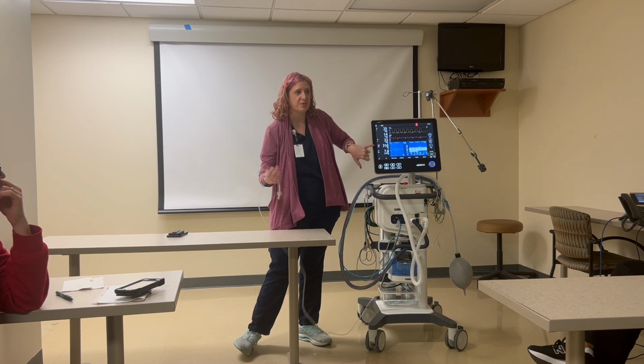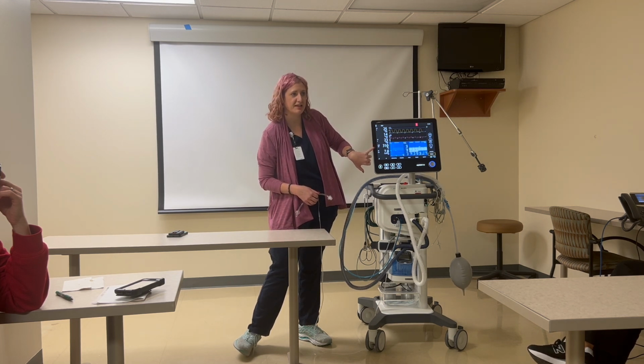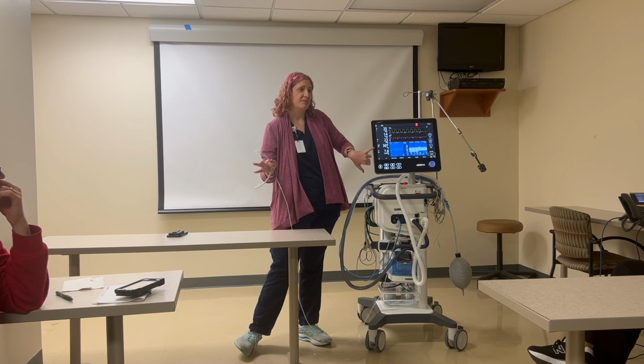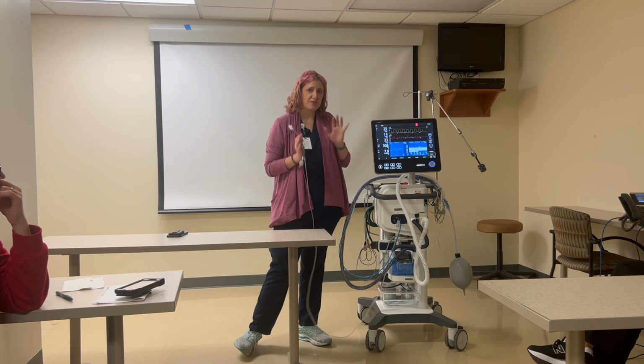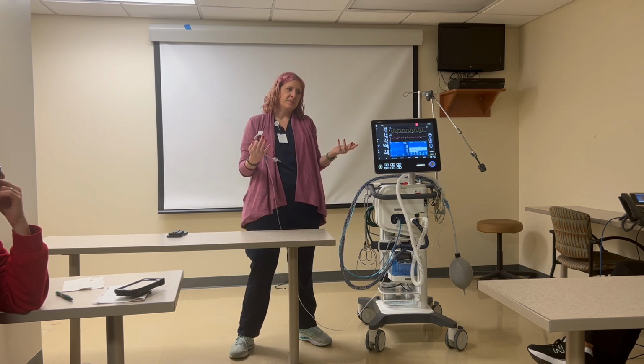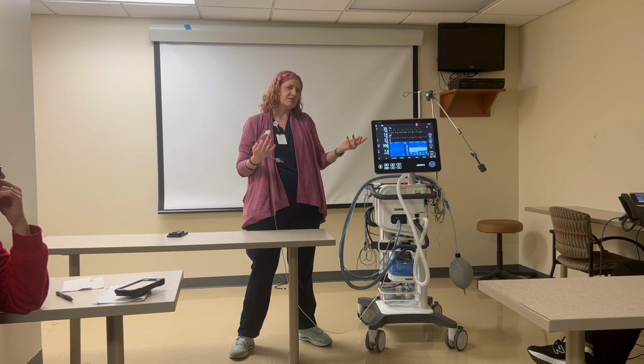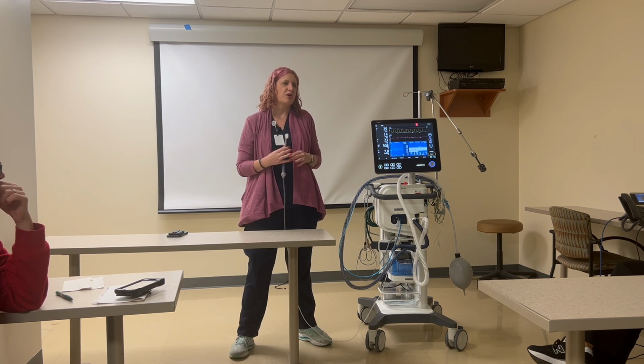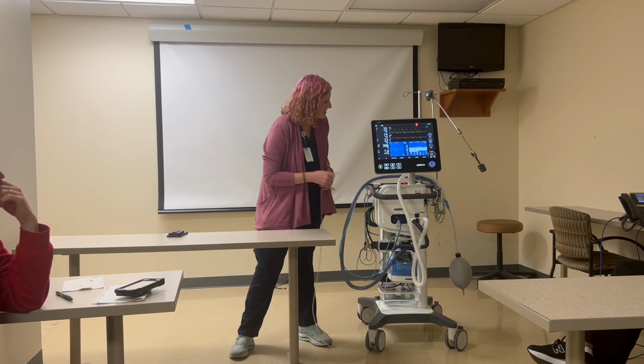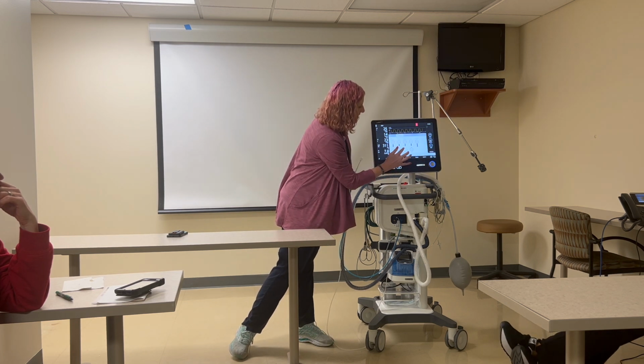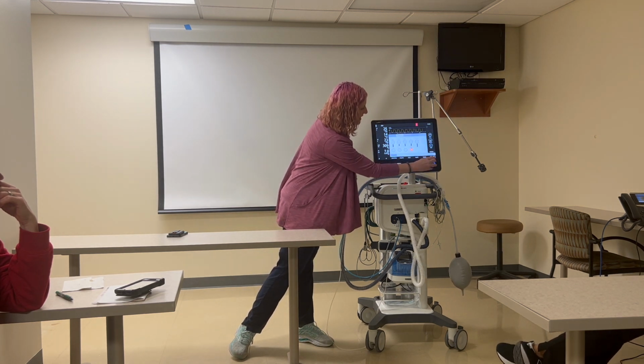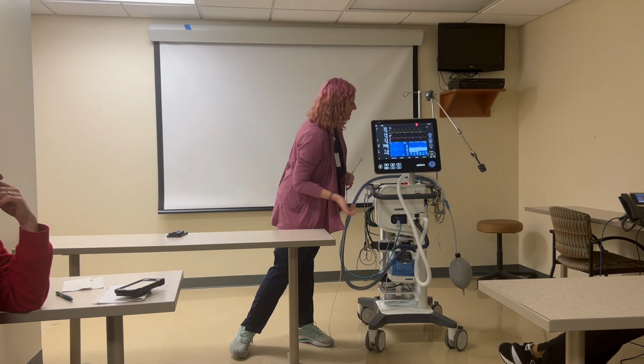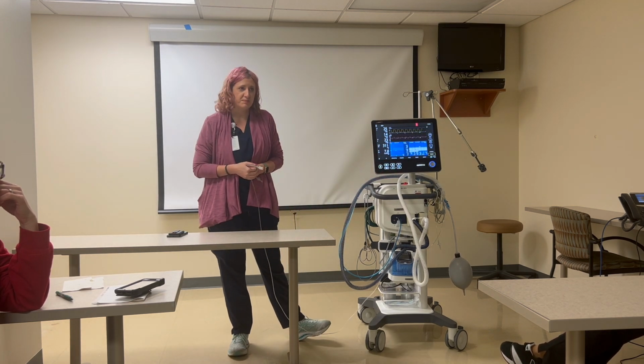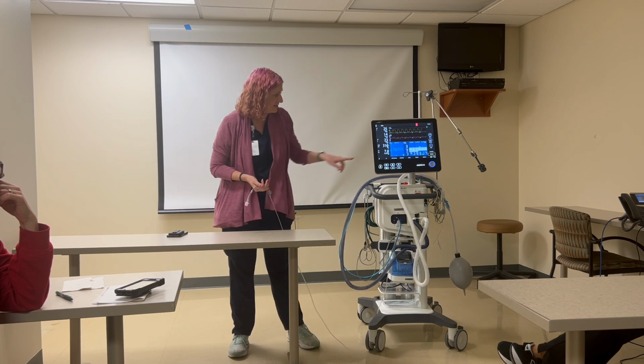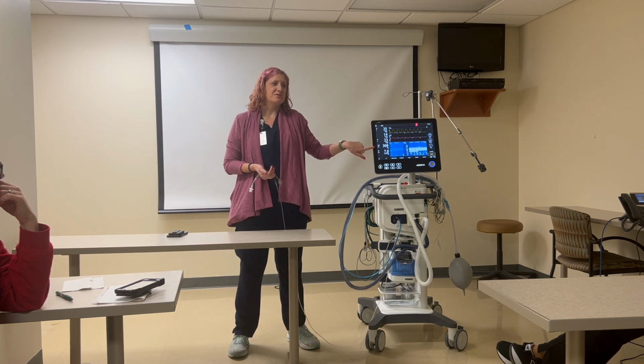If that patient were to take a smaller breath that was less than 190, depending on that rate, ASV might be okay with a smaller tidal volume. But if RT has those alarms too narrowed, you'll still get that alarm. So RTs are getting comfortable managing alarms as well, but if I increase this alarm and say I had it set at 300 because it's a 6'2" male and they shouldn't be having a smaller tidal volume than that, then right at 300, this might become a nuisance alarm.